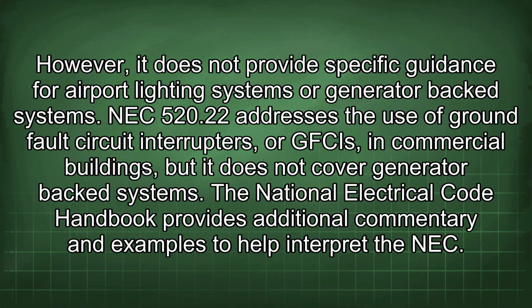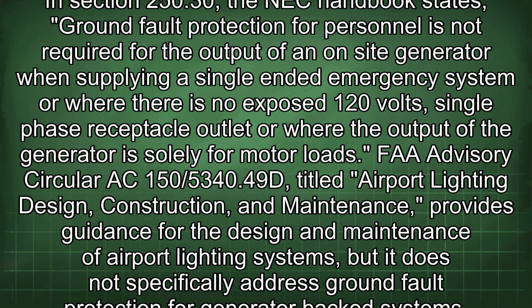NEC 520.22 addresses the use of ground fault circuit interrupters, or GFCIs, in commercial buildings, but it does not cover generator-backed systems. The National Electrical Code Handbook provides additional commentary and examples to help interpret the NEC. In Section 250.30, the NEC Handbook states, ground fault protection for personnel is not required for the output of an on-site generator when supplying a single-ended emergency system or where there is no exposed 120 volts single-phase receptacle outlet or where the output of the generator is solely for motor loads.